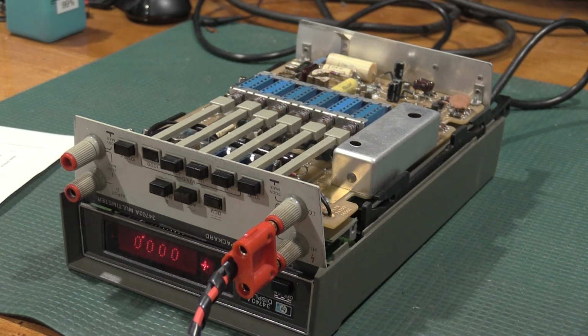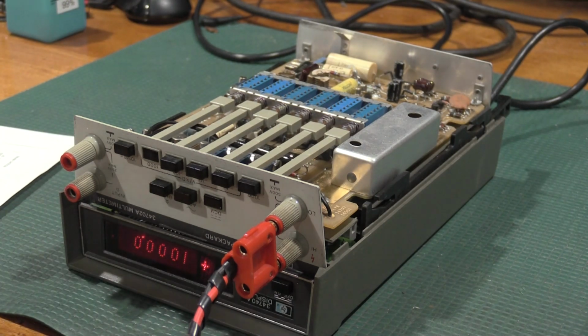Okay, here's 1000 volts. Not too bad for testing it or setting it at the bottom of its range. Kick this up to 1000. Right there. All right. Well, that's the DC ranges. Next is the AC ranges. Okay, our 1 volt AC is going to need a little bit of adjustment.